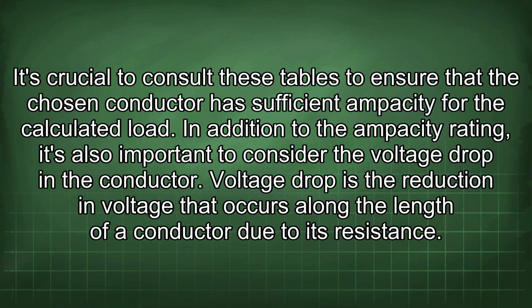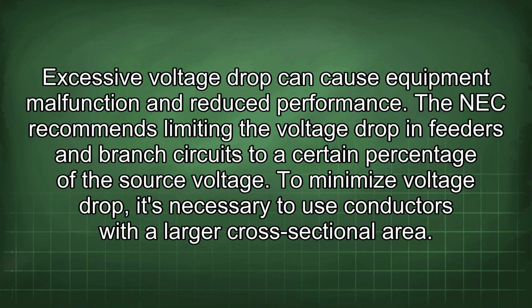In addition to the ampacity rating, it's also important to consider the voltage drop in the conductor. Voltage drop is the reduction in voltage that occurs along the length of a conductor due to its resistance. Excessive voltage drop can cause equipment malfunction and reduce performance.